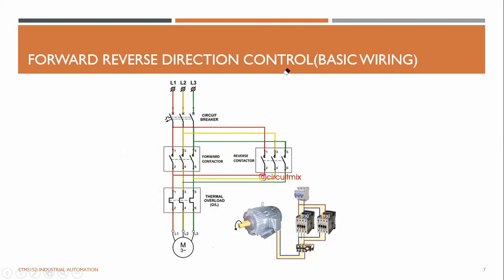So basically, the wiring, you can see, when this contact closes, L1 is connected to L1, L2 is connected to L2, and L3 is connected to L3, right? So it's a pretty straight path. And if you want to reverse the motor, you can now open this forward contact and close this reverse contact.